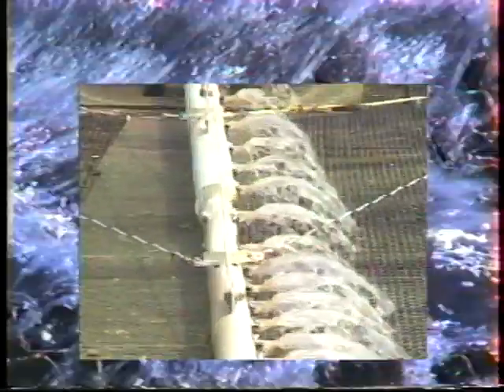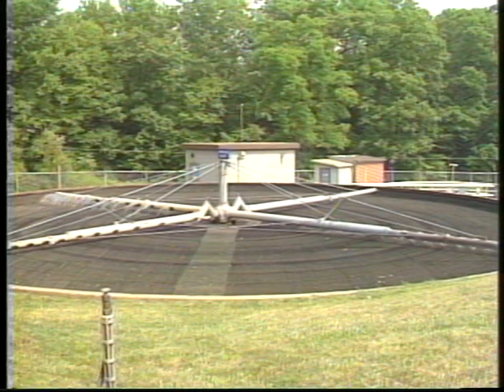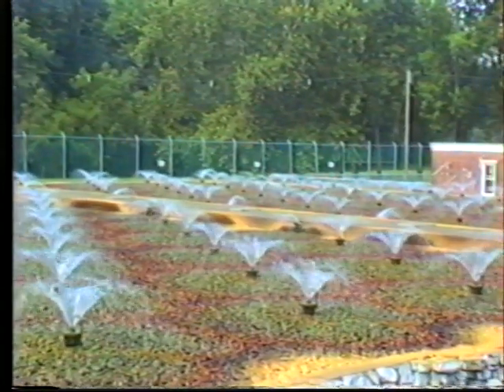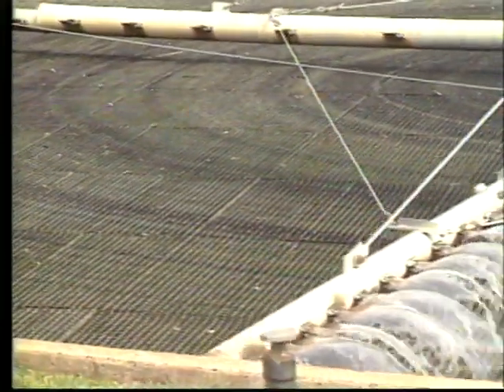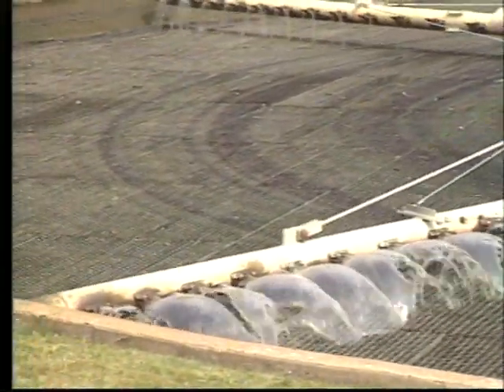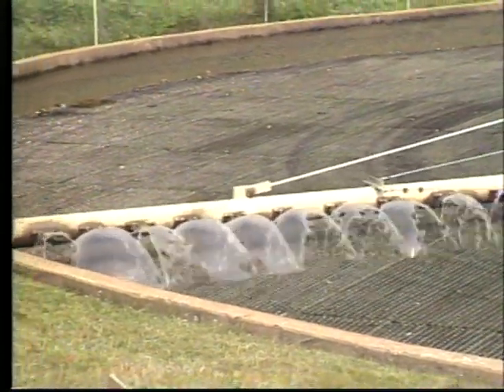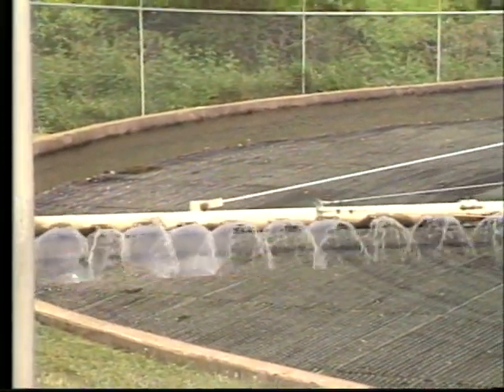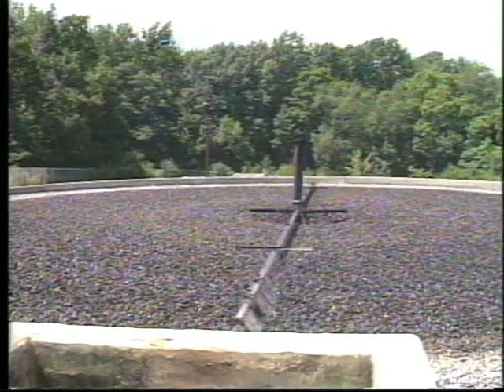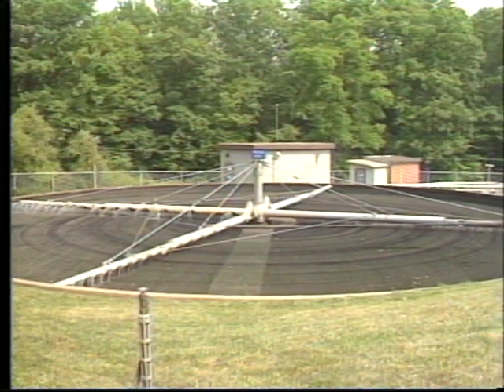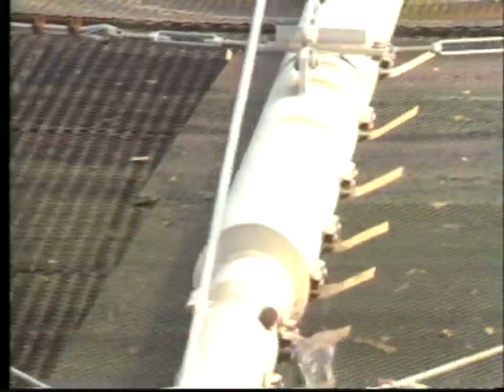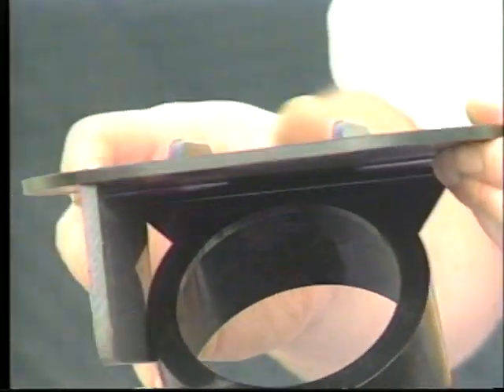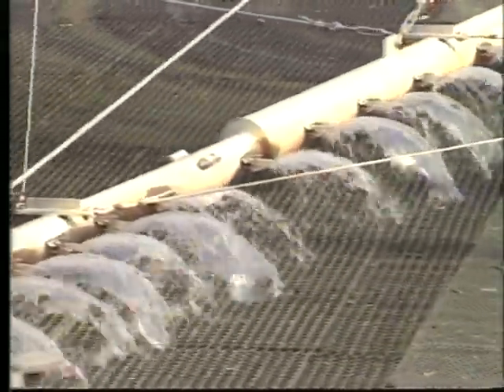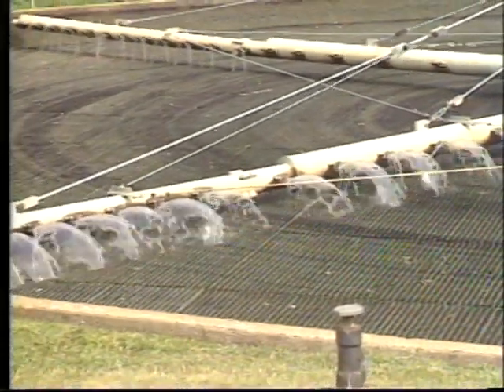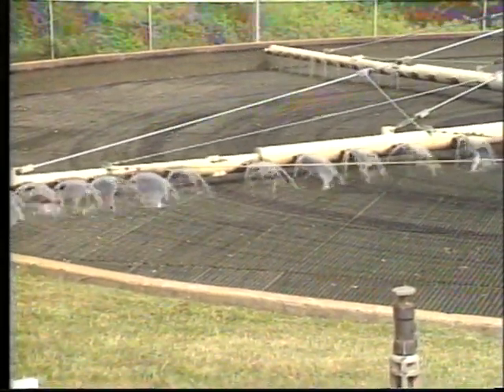Looking at the distribution system, we see that it may be either a rotating or a fixed orifice type of system. In either case, the job of the distribution system is to evenly distribute the water over the filter media. Rotating distributors are usually powered by the jet action of the wastewater discharging from the orifices. A rotating distributor may have either two or four arms. The orifices are usually adjustable and are equipped with splash plates to evenly fan the wastewater over the media. The orifices are closer together as you get to the outer part of the distributor to facilitate an even distribution of the wastewater over the entire bed of media.